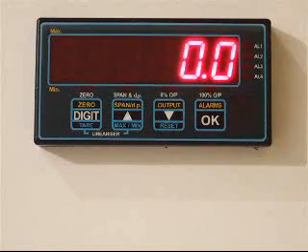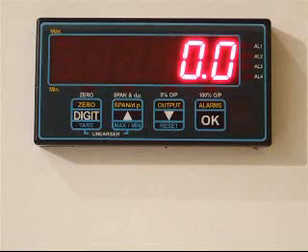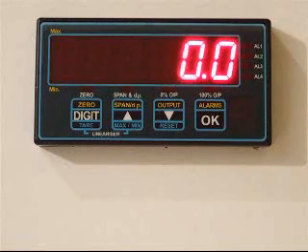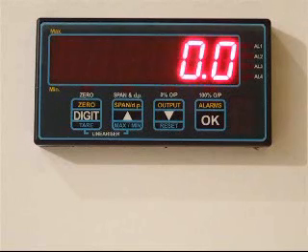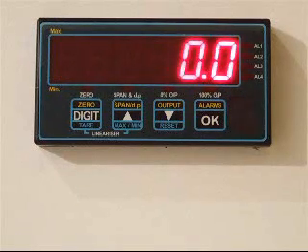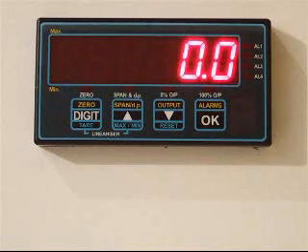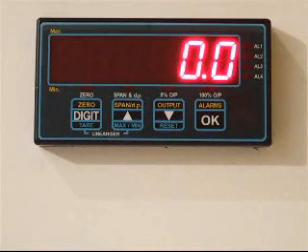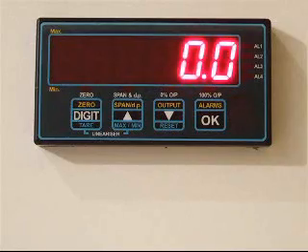By increasing the filtering value, you can average the reading over a period of time, which will give you a more stable response. To access the filter variable, make sure the meter is unlocked. At the back of the meter, there's a calibration lock switch - make sure that's switched off.